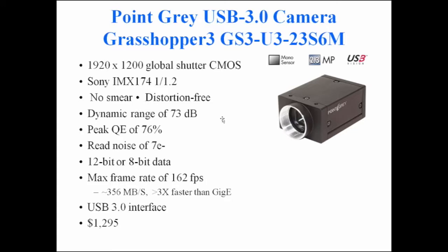There's also a CMOS camera with really high performance: a couple of megapixels, 73 dB dynamic range, very high quantum efficiency, read noise of only 7 electrons (comparable to cooled CCD cameras), and it can do 162 frames per second — about 360 megabytes per second, three times faster than GigE. With USB3 interface, it's $1,300. This is the camera currently used for tomography at Sector 13, originally bought for pink-beam tomography because at $1,300 it's affordable to replace, but the data quality is high enough to use for monochromatic beam too.